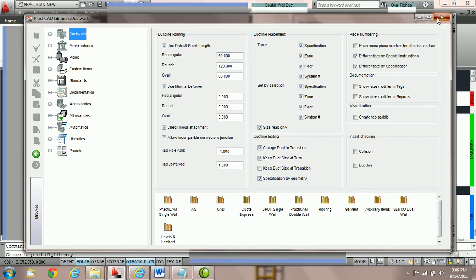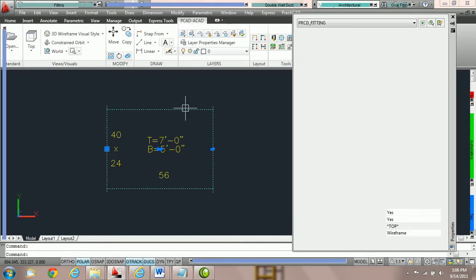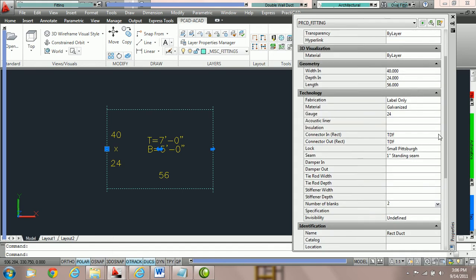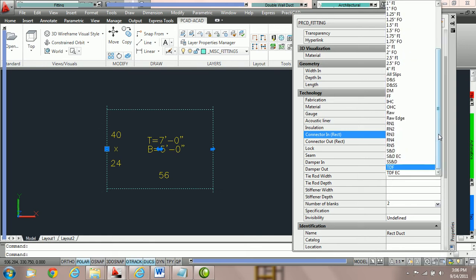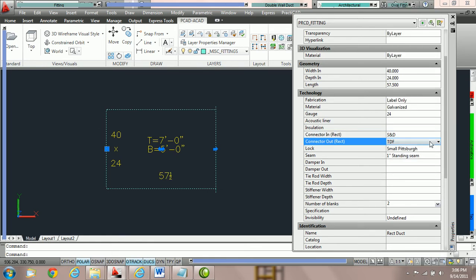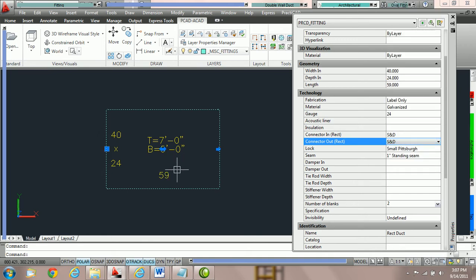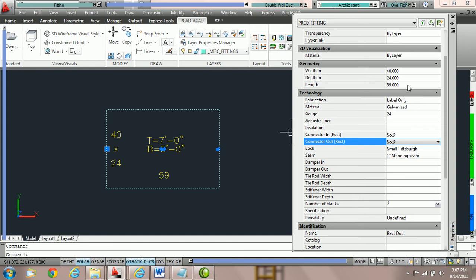We're going to exit out of the library. By clicking on the duct and coming over to the AutoCAD property box — now if we make any change to the connectors, for example switching both connector in and connector out to slip and drive — you can see that this customer has it set to lose a half inch on each side, so our finished length is going to be 59 inches, coming from a 60-inch default stock length. It will stay on label only up until you make a change to your length.